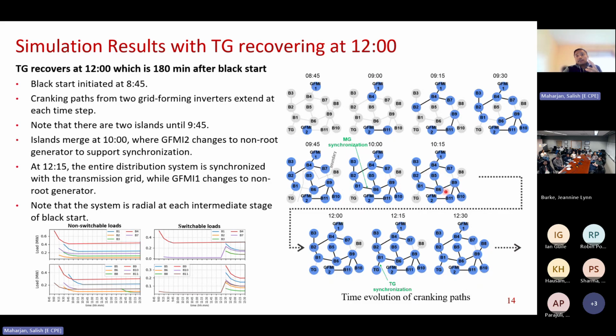And after the synchronization, it continues in this state all the way until 12. So at 12, you see that the transmission grid has come online, but still it's not connected to the distribution system. And at 12:15, the synchronization happens, and grid forming inverter 1 also gives up its root bus status. So basically at 12:15, there's only one root bus, which is the transmission grid. Okay, and lastly, bus block B8 is picked up at 12:30. So this is the whole decision that is provided by the blackstart algorithm.